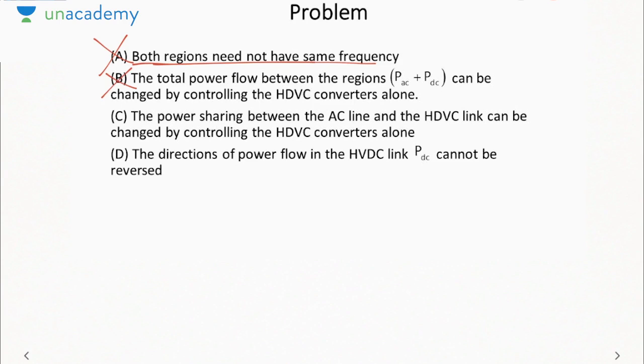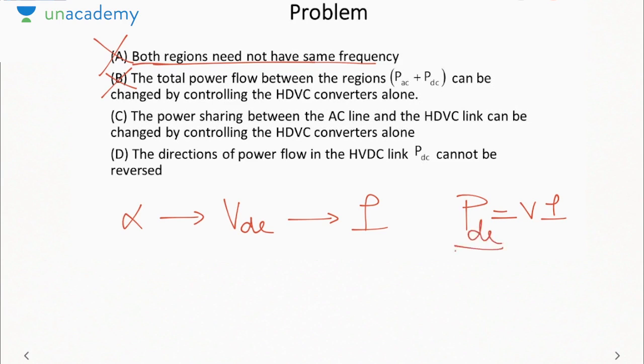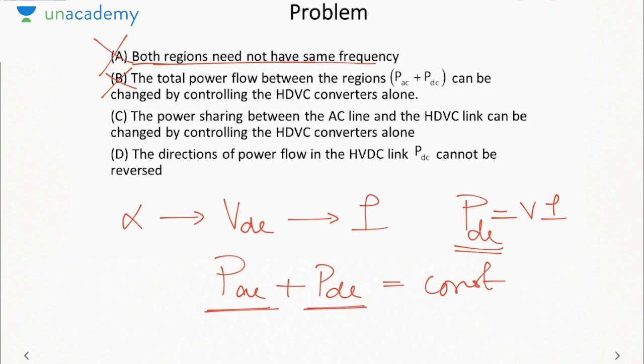Power sharing between AC and DC can be changed by controlling HVDC converters. Now by changing alpha, we can control VDC, we can control I. Hence we can control power, which is equal to VI. So DC power can be changed, but total power, that is PAC plus PDC, should be constant as it is dependent on load. So we can change the sharing of power between AC and DC by controlling the HVDC converters. Because if you change PDC, PAC will automatically change to keep PAC plus PDC constant.